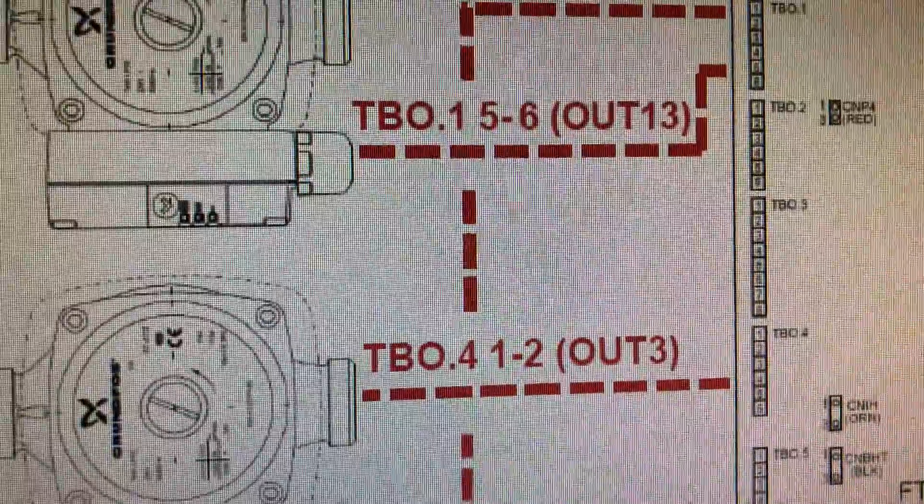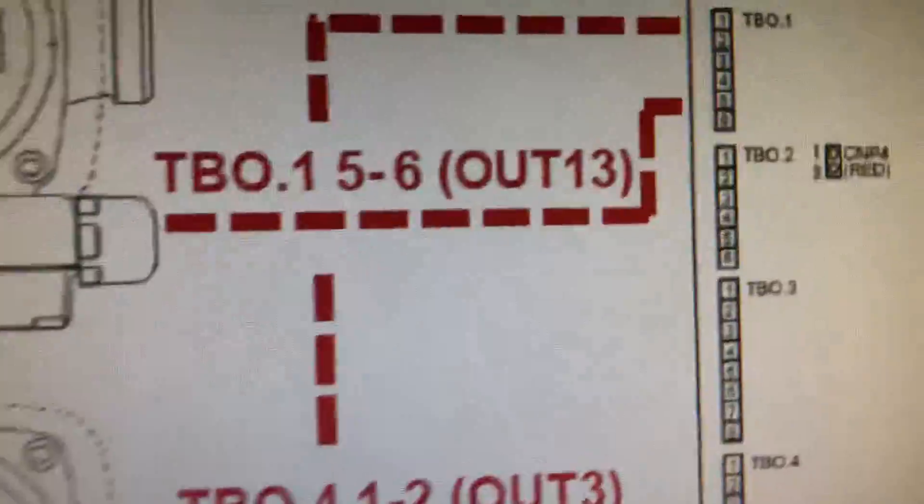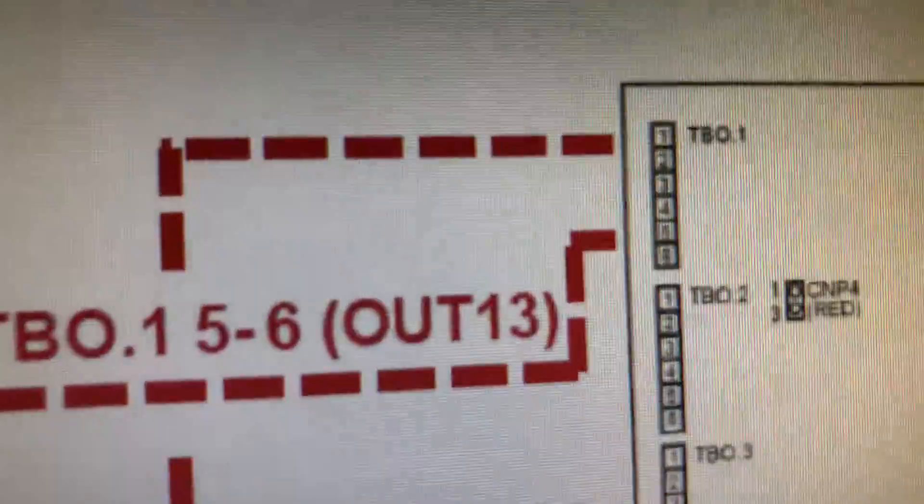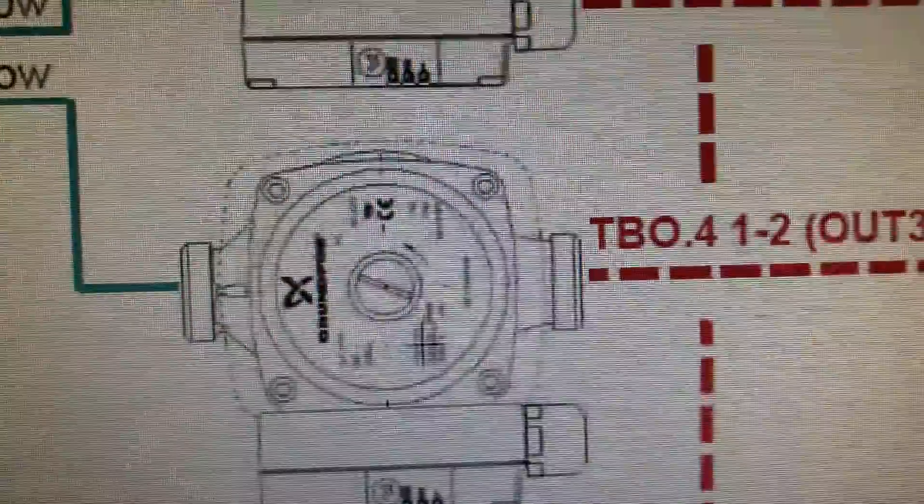That is wrong. TBO 1, 5 and 6 does not go to Zone 1. Look at the outs. Out 13 on the board which is 5 and 6. Out 3 on the board is not 1 and 2.